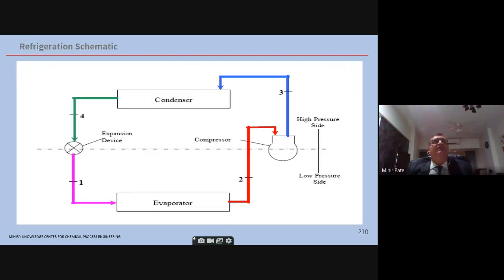Here we see a refrigerant schematic. So refrigeration is a simple schematic. Again, refrigeration has many types. You can have an ammonia vapor absorption system. You can have a lithium bromide vapor absorption system. Here I have shown the conventional system, which is basically you have a compressor. The refrigerant you are compressing, taking to a condenser, which can be cooling water or air cooled.